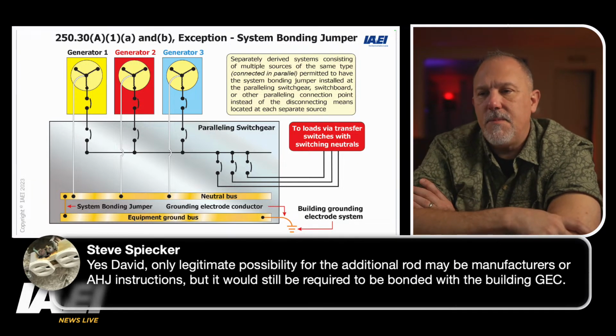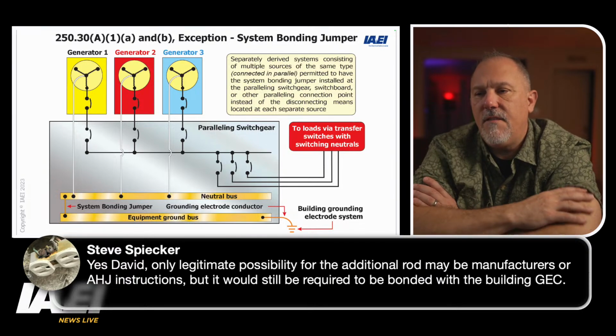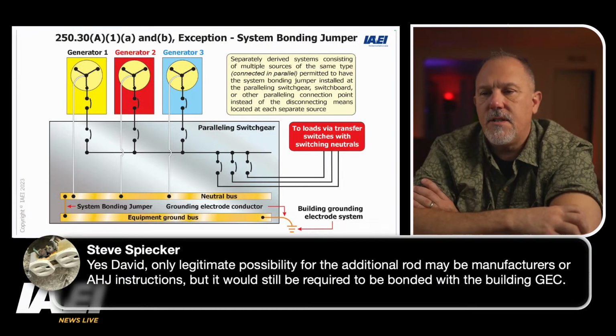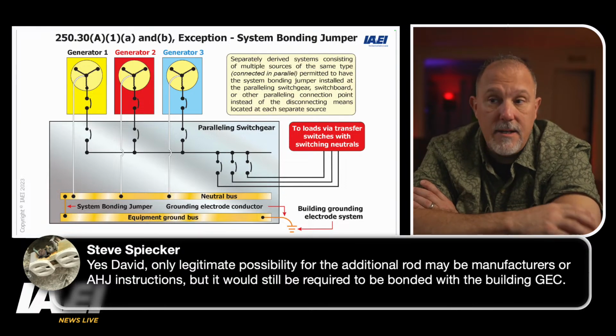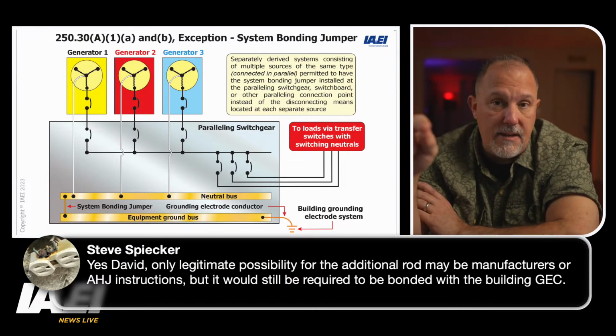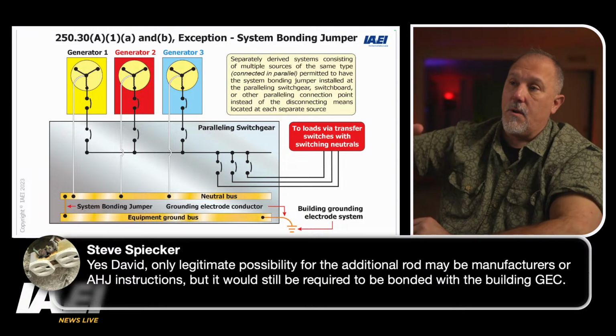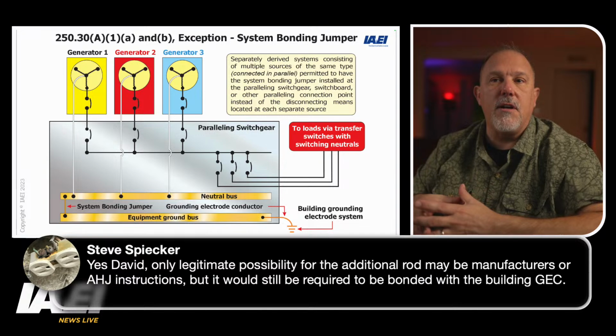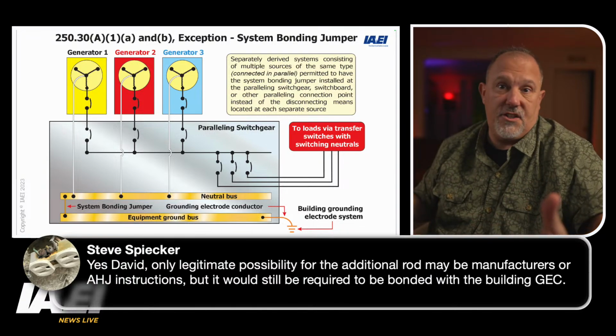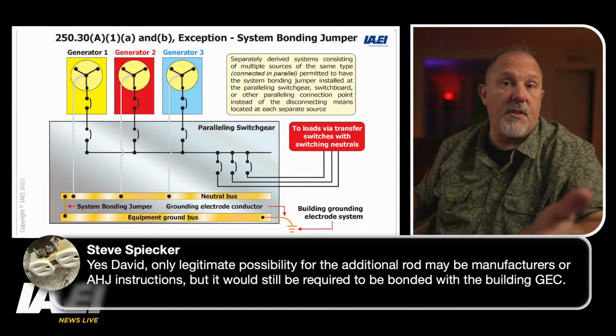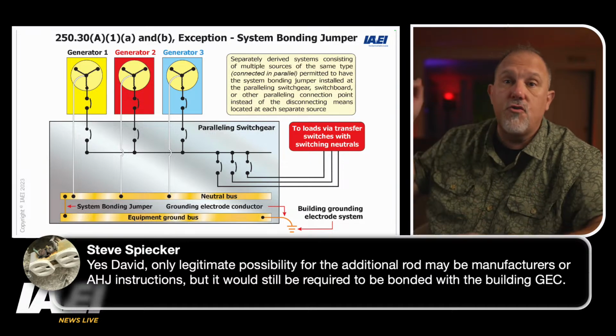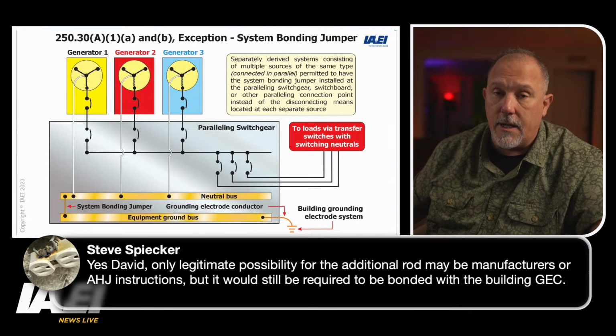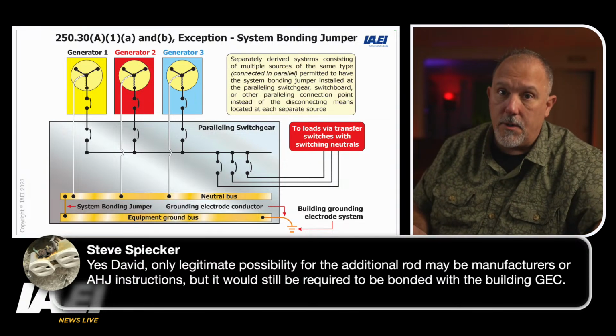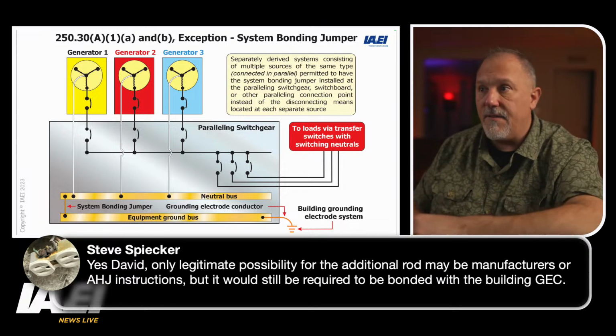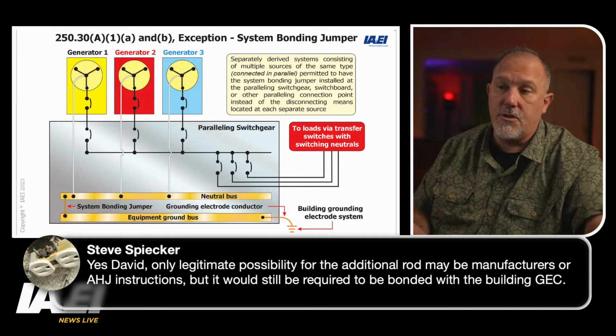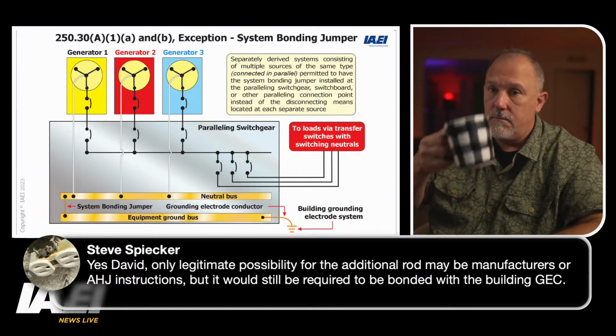Only legitimate possibility for the additional rod may be manufacturer's or AHJ instructions, but it would still be required to be bonded. Yes. Now, and you know what? Honestly, Steve, I'm okay if you put another rod in, as long as you connect that as part of the grounding electrode system. I can do that. I don't have any problem with that. There's nothing that would prohibit that. Now, if you drove that rod and you did not make it a part of the grounding electrode system, that's a problem. But you can drive that rod, put that as part of the grounding electrode system, and you're good to go.